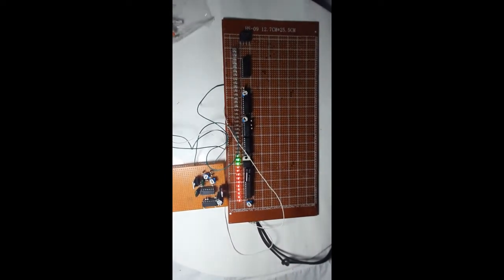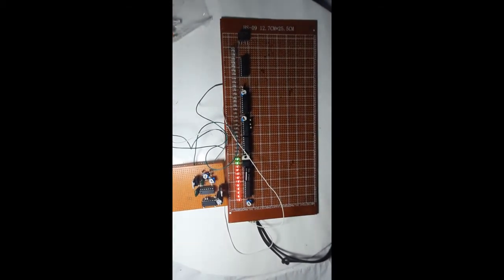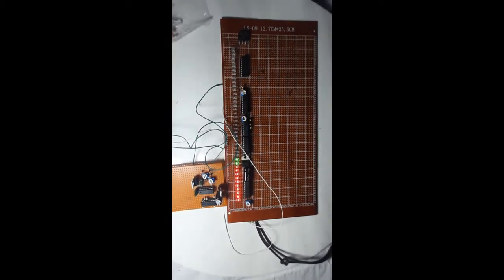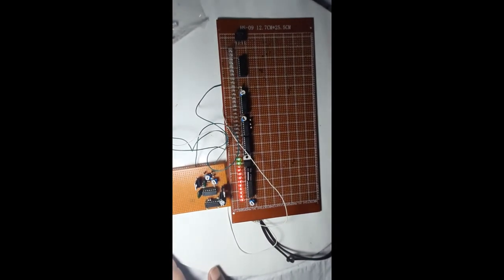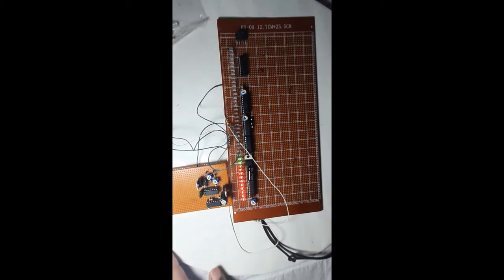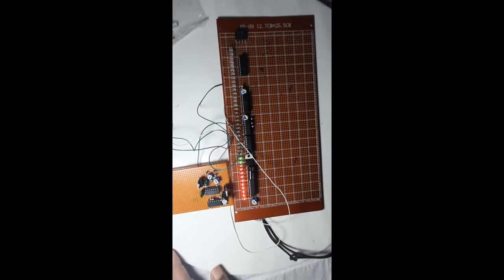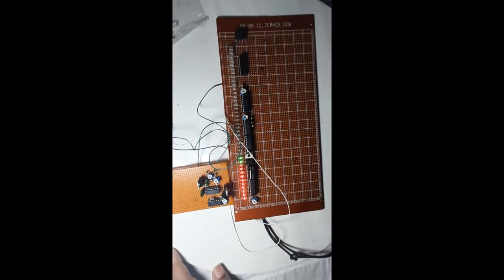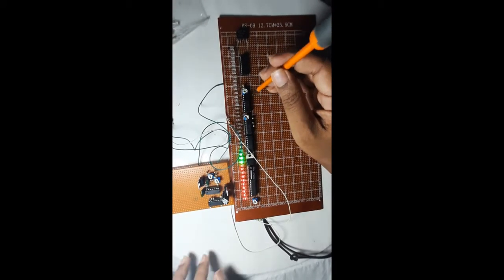So when we manipulate the span potentiometer, this error has been introduced. So this error has to be eliminated now. To eliminate that error, this is a 0 error basically, as I told you, right? So we have to correct the 0 error now once again, because we followed the wrong method. Because we initially corrected the 0 error, then the span error. Now things have gone wrong. Now we have to come back to 0 error once again, right? So now this is the 0 error adjusting potentiometer.